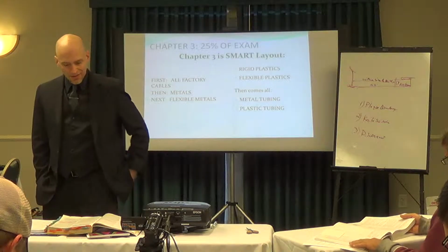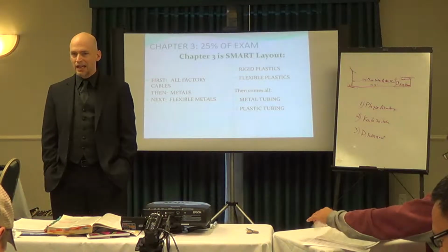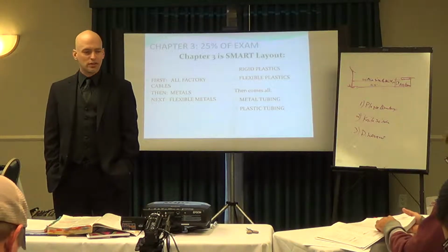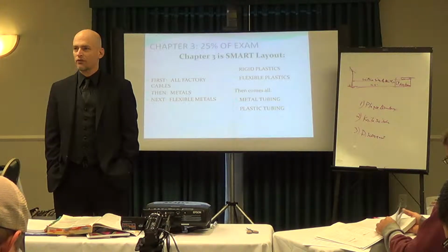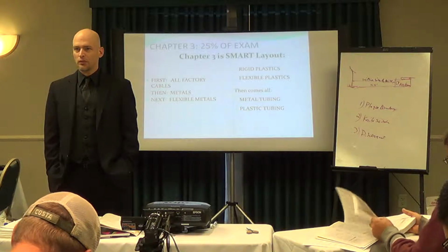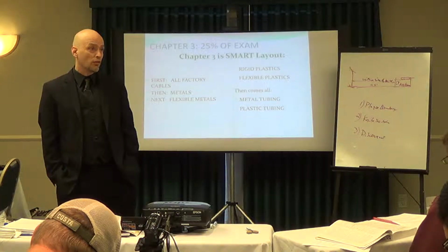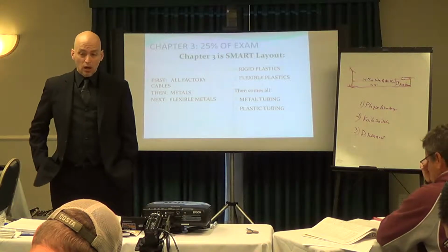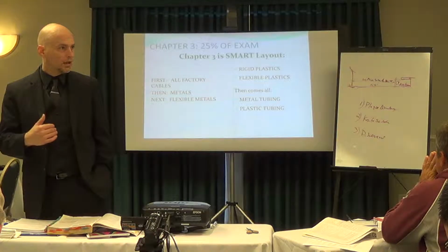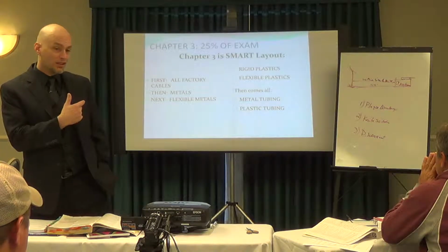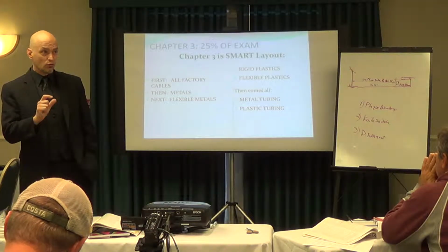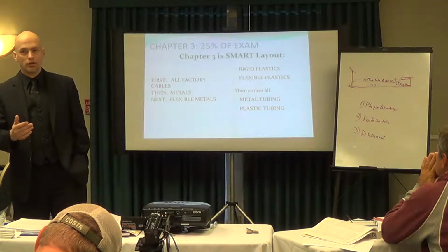On page 29, the defined term of "in sight" is what? How many feet? 50 feet. I can see just as clearly at 55 feet as I can from 50. It won't make a gnat's hair worth of difference to me, because to me that's still within sight. I can physically see a lot further than 55 feet, right? But the defined term within the code is exactly 50 feet or less. So they can tell you that it's within sight, and there's nothing wrong with that. It's true, but as it's defined by the code, it's not within sight.